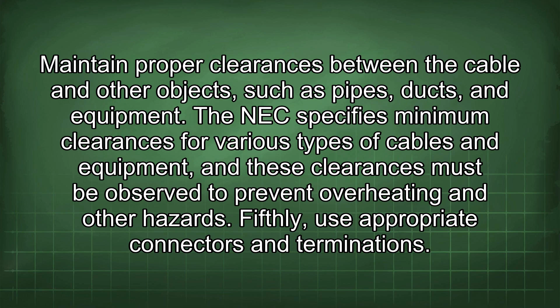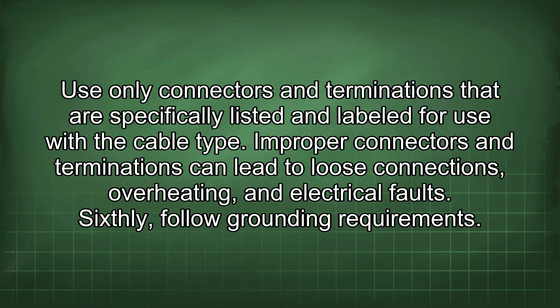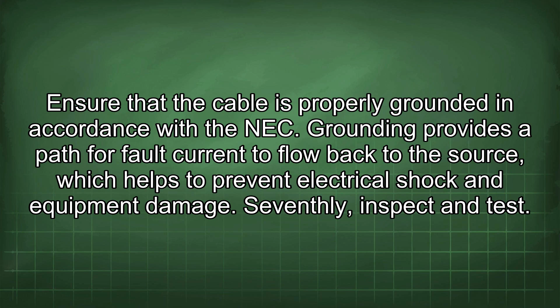Fifthly, use appropriate connectors and terminations. Use only connectors and terminations that are specifically listed and labeled for use with the cable type. Improper connectors and terminations can lead to loose connections, overheating, and electrical faults. Sixthly, follow grounding requirements. Ensure that the cable is properly grounded in accordance with the NEC. Grounding provides a path for fault current to flow back to the source, which helps to prevent electrical shock and equipment damage.